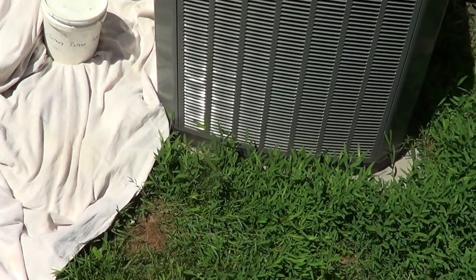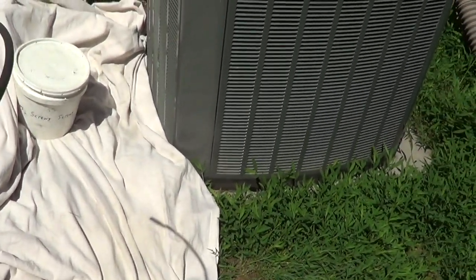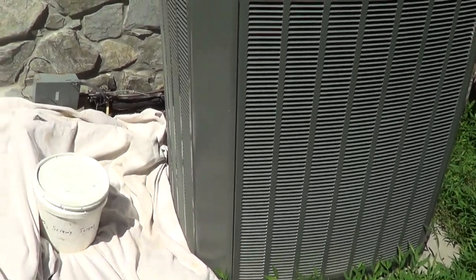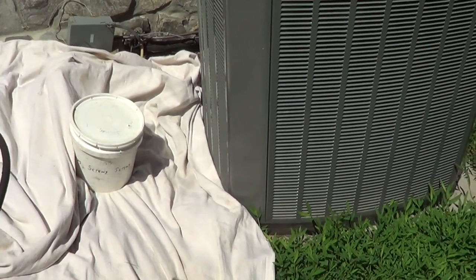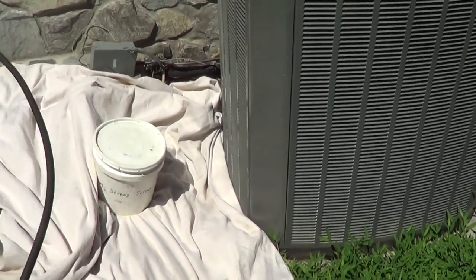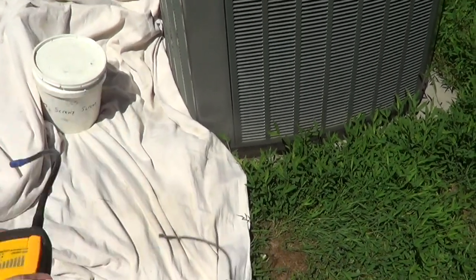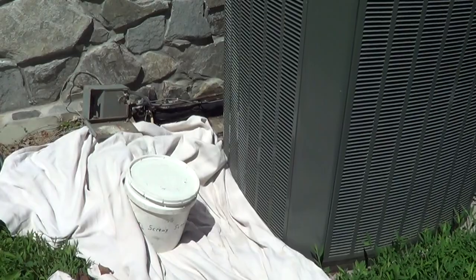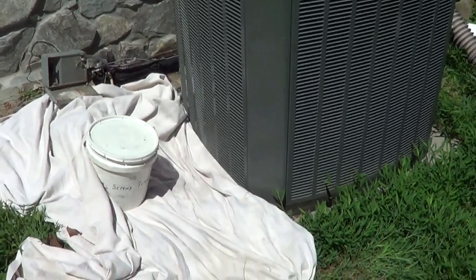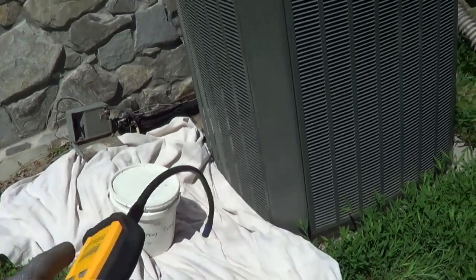I don't have my ultrasonic — I loaned it to a plumber for gas testing. If I had ultrasonic I could go in and listen for hissing, and that would find it really fast because it's a large leak. But I'm going to show you an alternative method to find the leak without destroying your leak detector — or destroying the sensor — in the process.